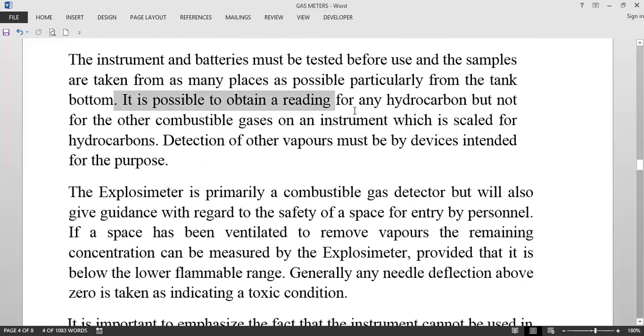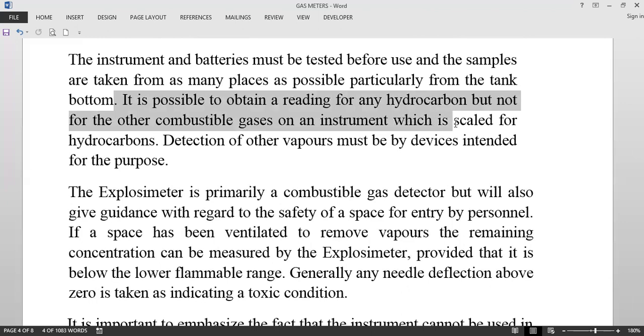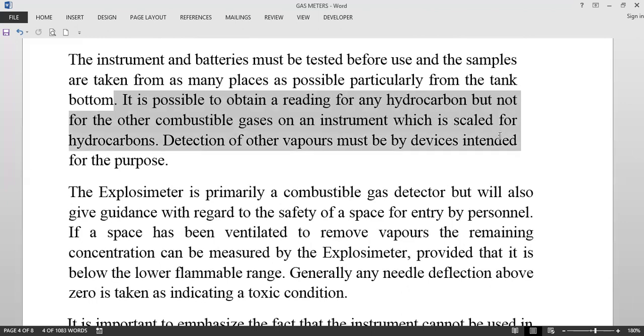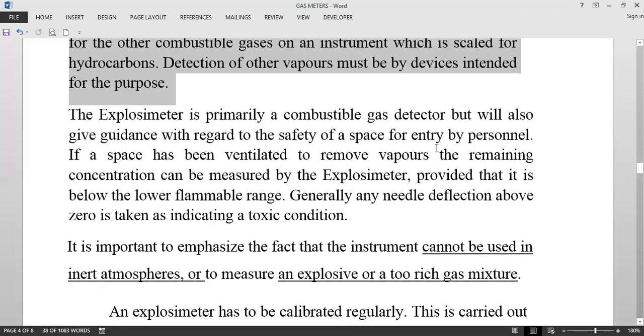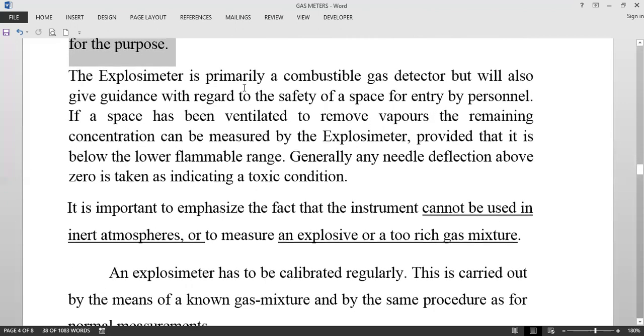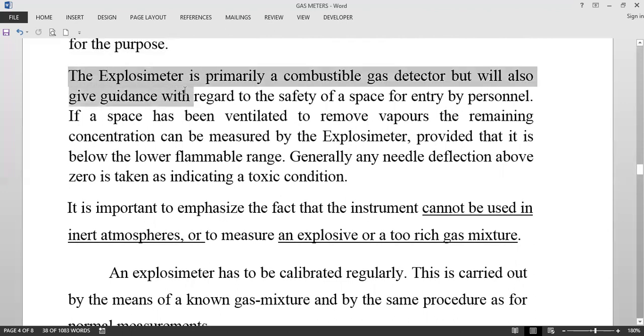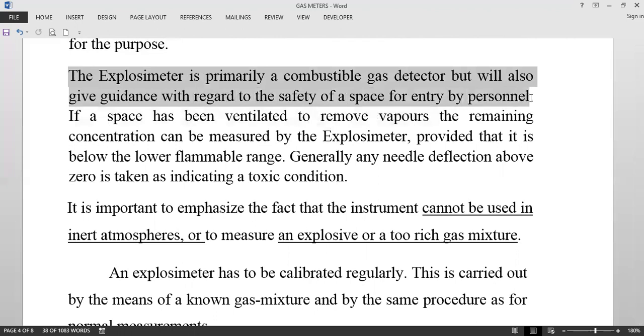It is possible to obtain a reading for any hydrocarbon, but not for other combustible gases on an instrument scaled for hydrocarbons — detection of other vapors may require devices intended for that purpose. This explosimeter is primarily a combustible gas detector but will also give guidance with regard to the safety of a space for entry by personnel.